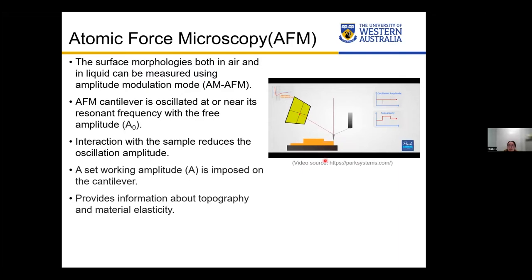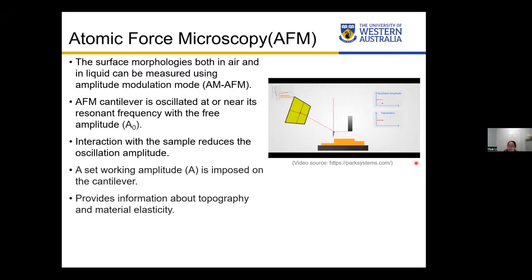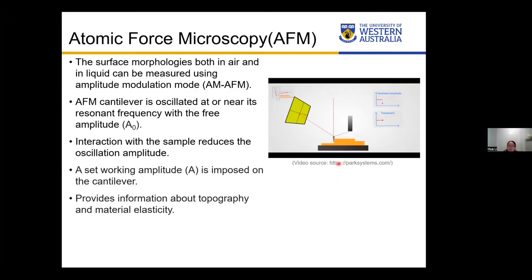As the cantilever moves close to the surface, the interaction with the sample reduces the oscillation amplitude. A set-point amplitude, lower than the free amplitude in air, is imposed on the cantilever to guide it to move up and down to map surface morphology. We can also achieve other information such as elasticity. This is achieved by a feedback loop that constantly readjusts the average tip-to-sample distance. That is how AFM works.